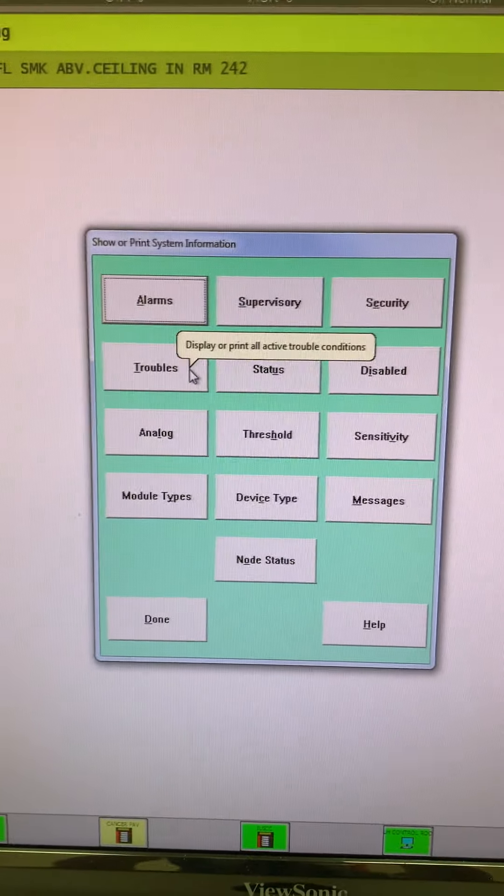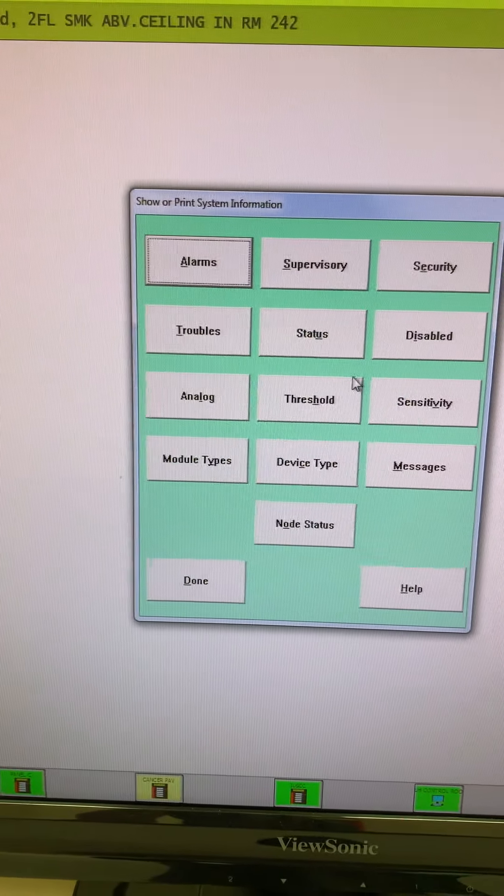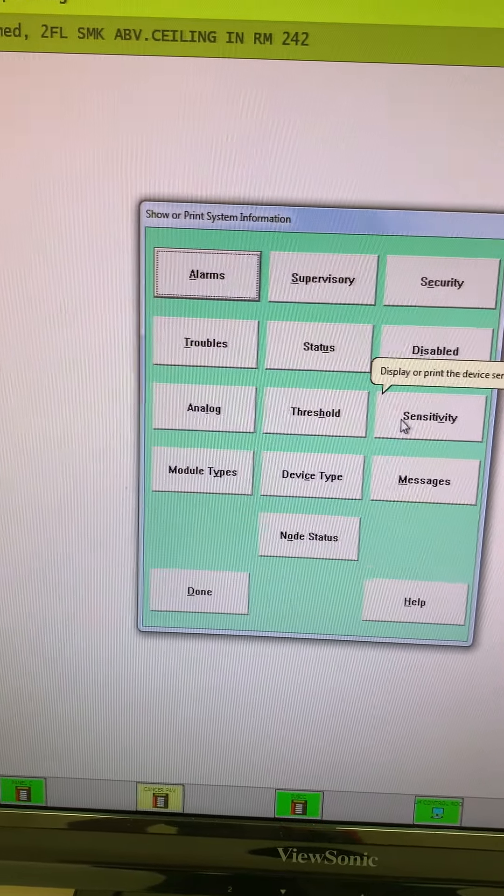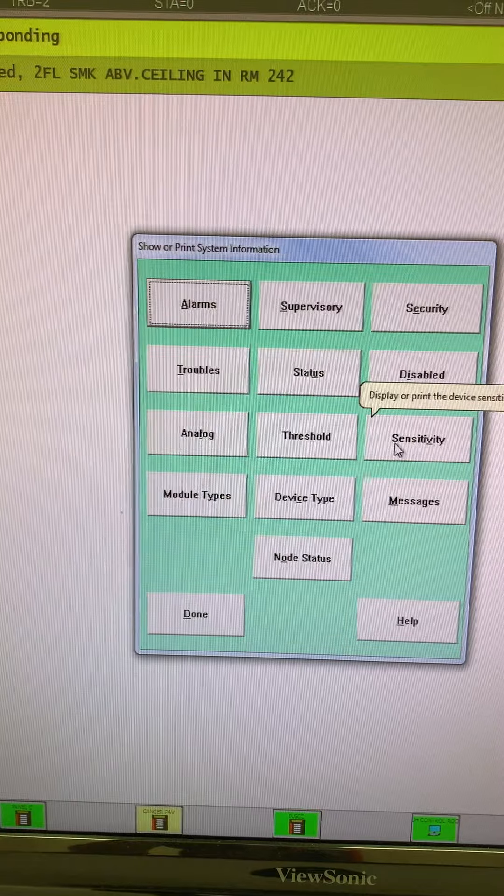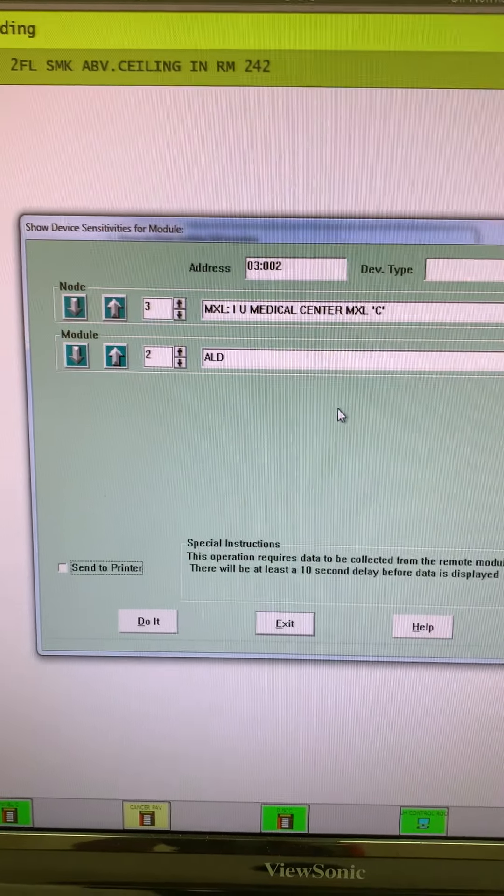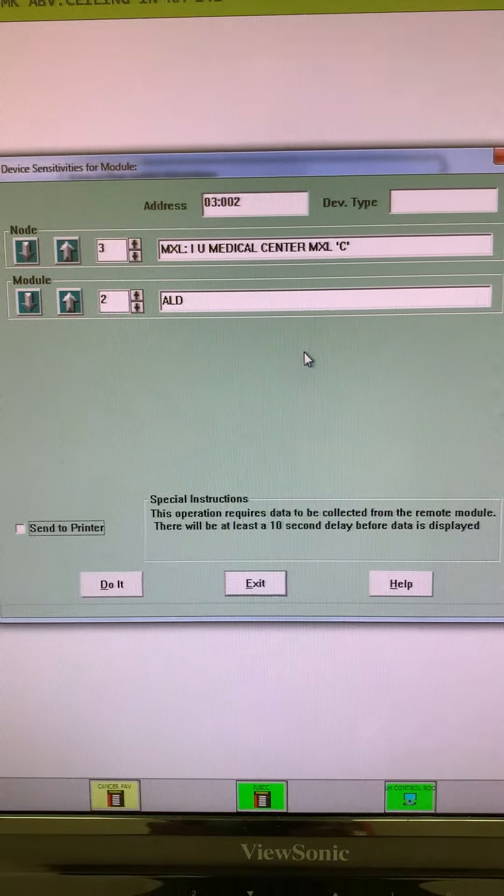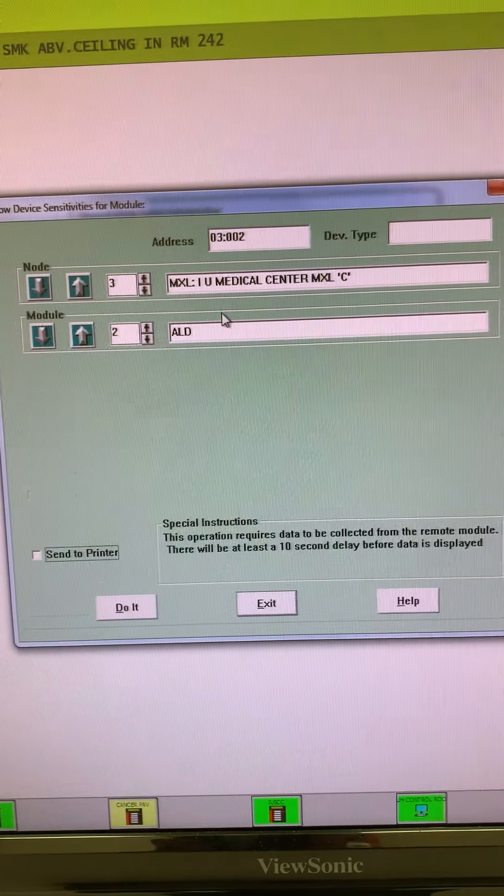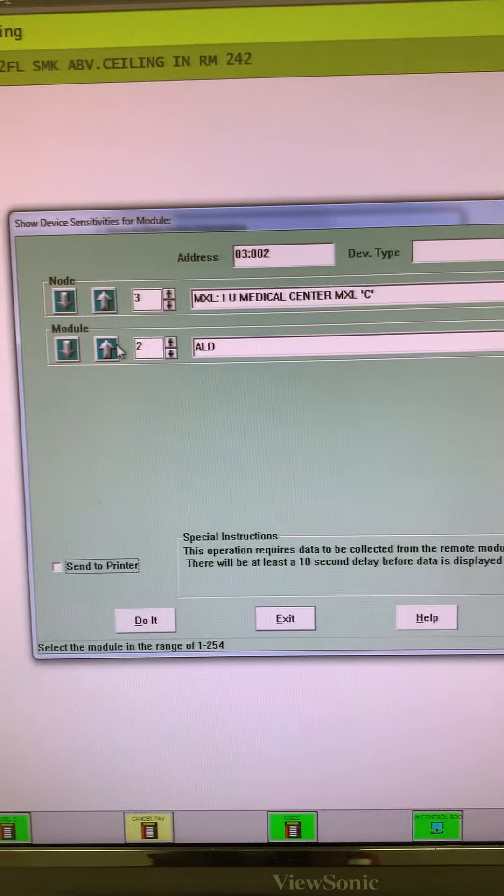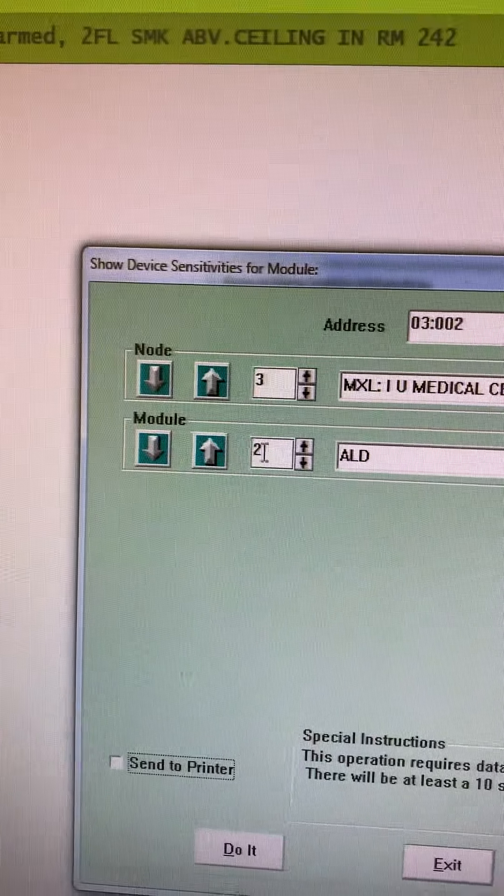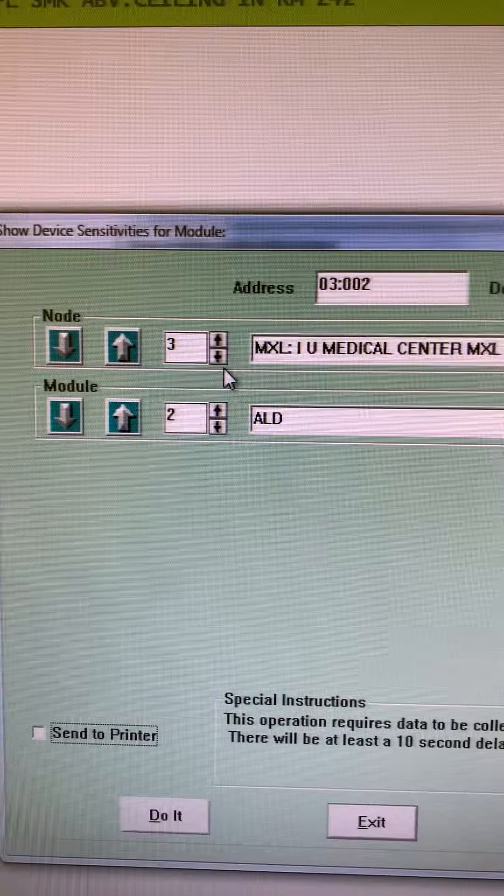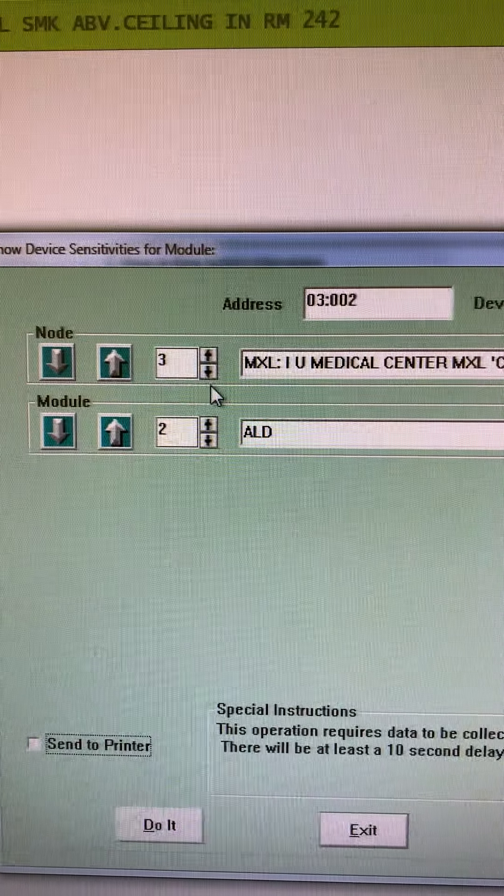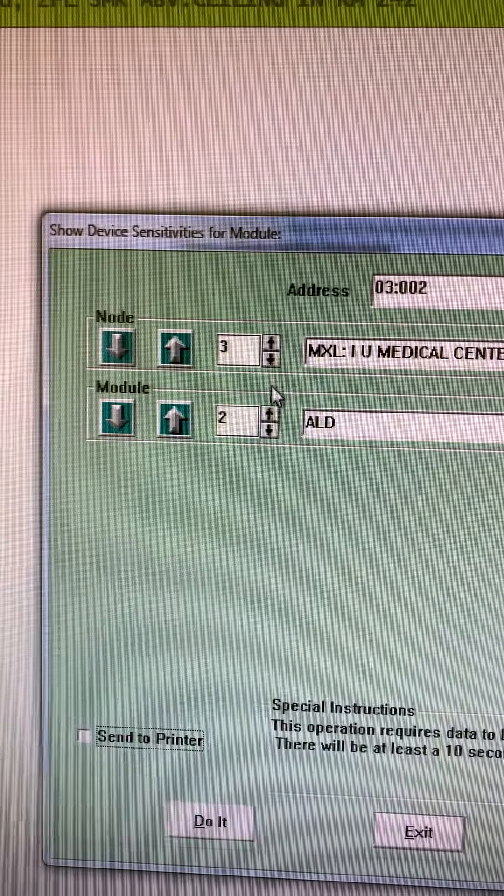One thing that's very common is we like to monitor the sensitivity of our smoke and duct detectors. I can click that and basically how this works is I can select my node and then I'm going to select the module. Module is another word for loop. So I'm on node, I'm in the medical center, it's an MXL panel, and it's Panel C. I'm going to look at loop two.